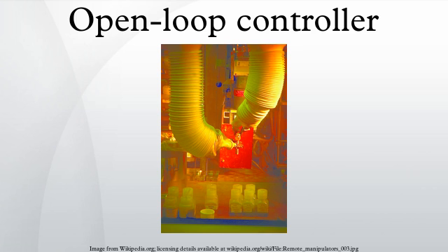If the load were not predictable, on the other hand, the motor's speed might vary as a function of the load as well as of the voltage, and an open-loop controller would therefore be insufficient to ensure repeatable control of the velocity. An example of this is a conveyor system that is required to travel at a constant speed. For a constant voltage, the conveyor will move at a different speed depending on the load on the motor. In order for the conveyor to run at a constant speed, the voltage of the motor must be adjusted depending on the load. In this case, a closed-loop control system would be necessary.